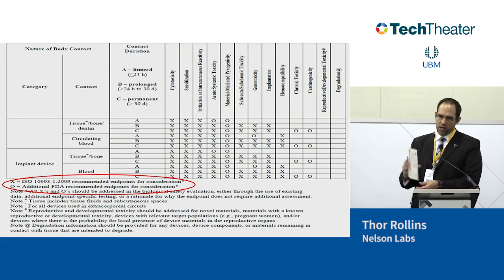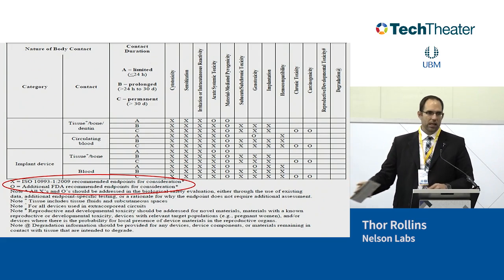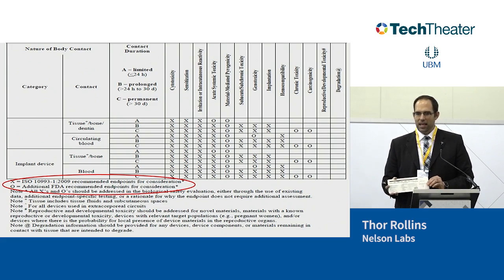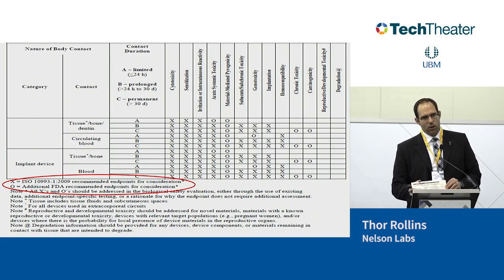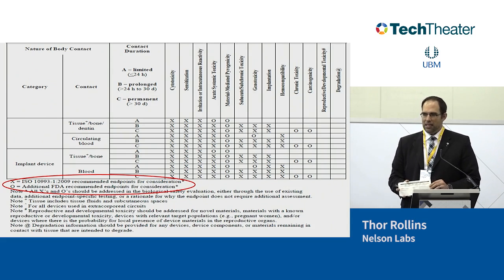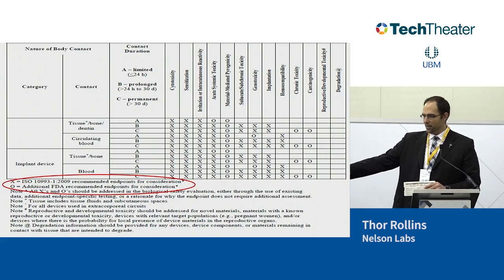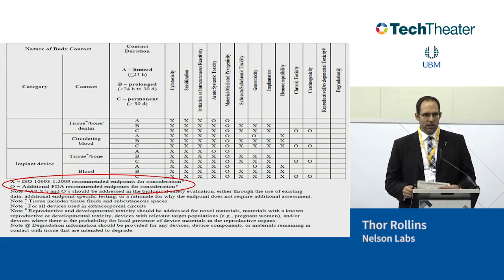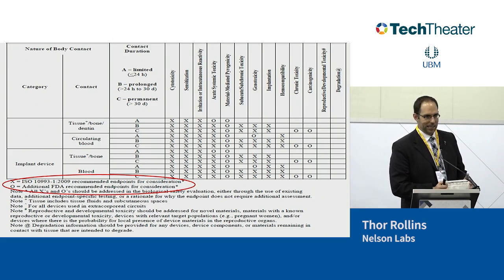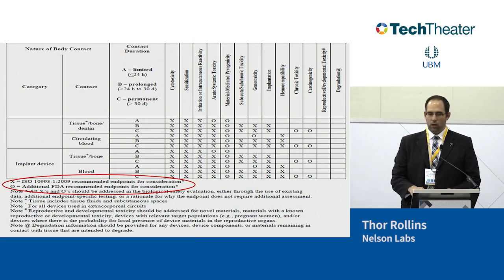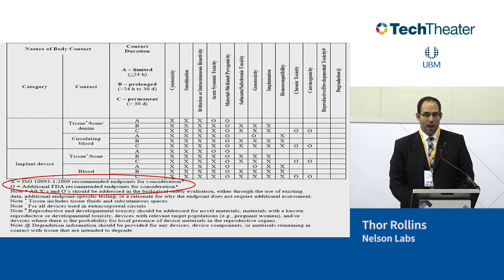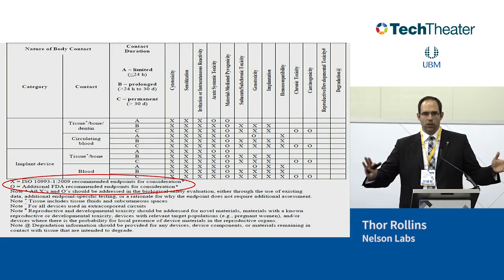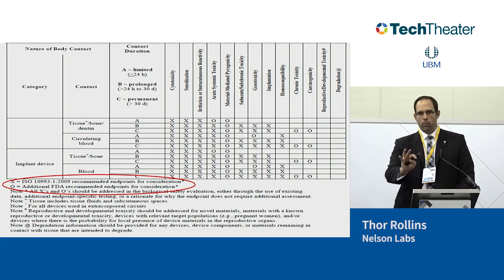So the FDA, if you look at our slide rule, has always had the circles in their G95. Those circles were tests that were just maybe considered necessary if the reviewer felt there was a reason to do the tests. Now, with this new chart, the FDA is requiring you to assess those endpoints, not just the X's, but the circles. So if you have a circle, you still have to assess that endpoint. Doesn't mean you have to test it, but we have to assess that endpoint. So the FDA is saying, look, if we're doing a risk analysis, and we're not saying you have to test everything, then we're going to make you assess those circles too. You tell us why those circles aren't needed. We're not going to tell you when they are or when they're not. You tell us why you think it. You know your products better than we do. Tell us why those circles are going to be needed or not needed. Okay?